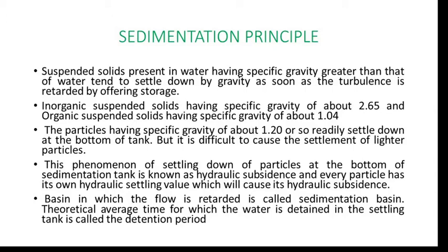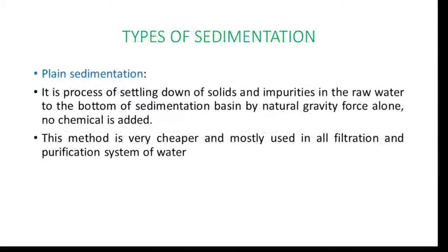Next, the principle: suspended solids present in water having specific gravity greater than that of the water tend to settle down by gravity as soon as the turbulence is retarded by offering storage. That means we have to store the water for a particular period, and that period is called the detention period. For that detention period, the suspended solids settle at the bottom of the tank by the specific gravity. This is the basic principle behind the working of a sedimentation tank.